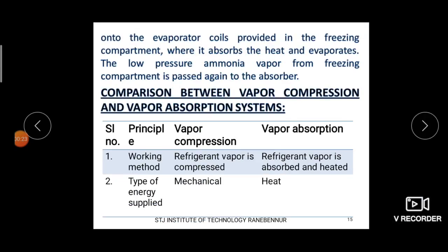The first difference is the working method. In case of vapor compression system, the refrigerant vapor is compressed. In case of vapor absorption system, the refrigerant vapor is absorbed and heated. In vapor compression system, by making use of a mechanical device like a compressor, you need to compress the vapors of the refrigerant in order to increase pressure and temperature and to circulate the refrigerant vapor throughout the cycle.